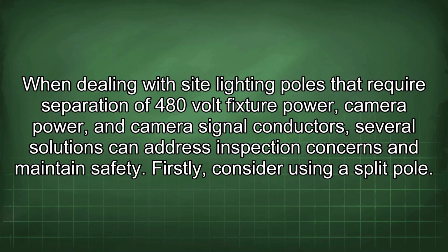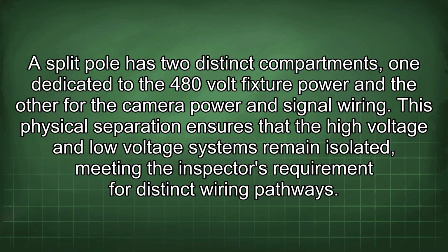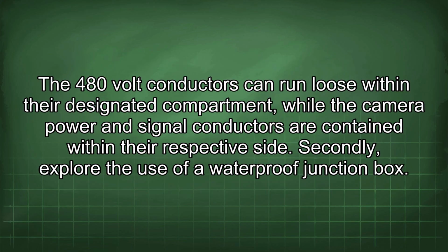When dealing with site lighting poles that require separation of 480-volt fixture power and camera signal conductors, several solutions can address inspection concerns and maintain safety. Firstly, consider using a split pole. A split pole has two distinct compartments, one dedicated to the 480-volt fixture power and the other for the camera power and signal wiring. This physical separation ensures that the high voltage and low voltage systems remain isolated, meeting the inspector's requirement for distinct wiring pathways.